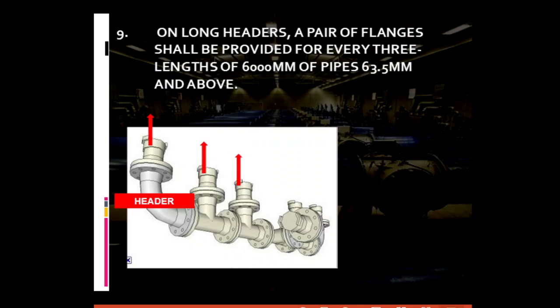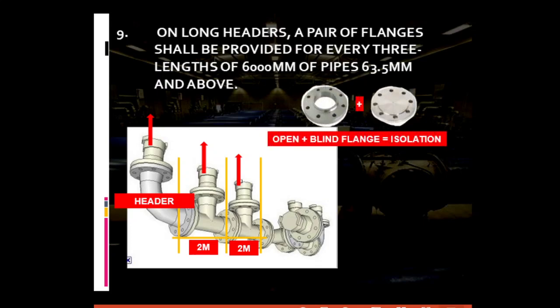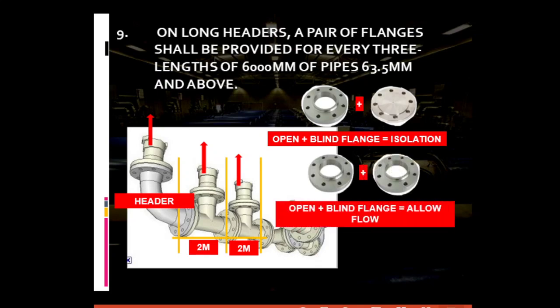For general piping requirement number nine: on long headers, a pair of flanges should be provided for every three lengths of 6,000 millimeters (6 meters) of pipes 63.5 mm and above. This allows shut-off or isolation of a malfunctioning pipeline, thus allowing continuous operation of the piping system without shutting down the whole system. For isolation, a pair of open flanges plus a blind flange is used. To allow fluid to flow, a pair of open flanges is used.